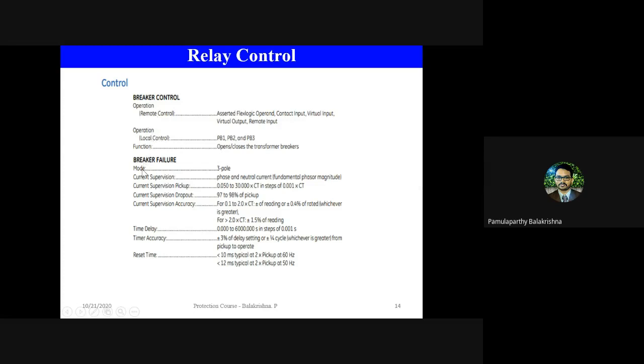Okay, then another important feature the relay offers is breaker failure detection. The relay detects a fault and sends a signal to the corresponding breaker, and the breaker is supposed to trip after some point of time, usually in milliseconds. So, what is a breaker? A breaker is a mechanical component. It has various driving mechanisms and operating switches.